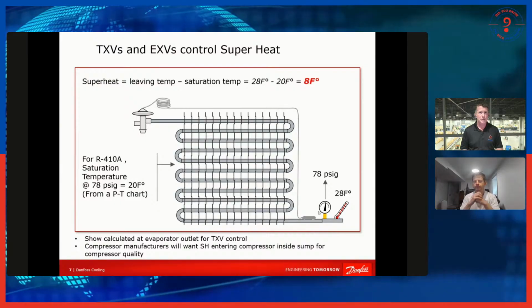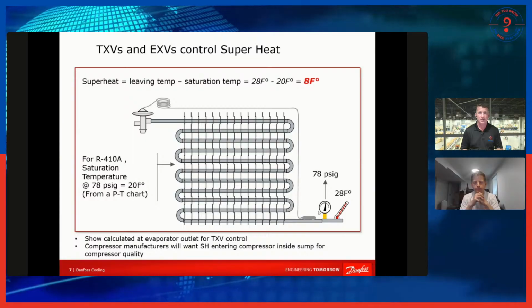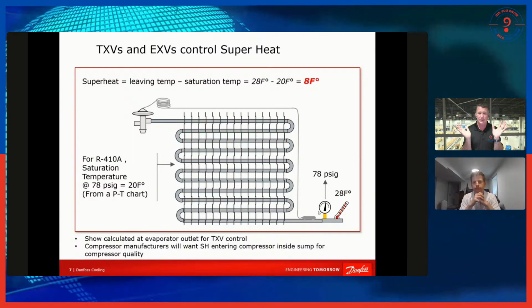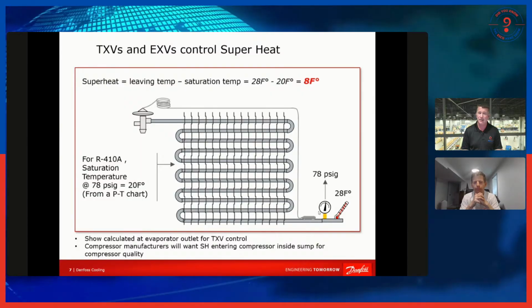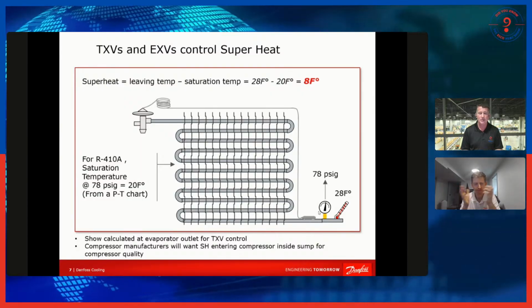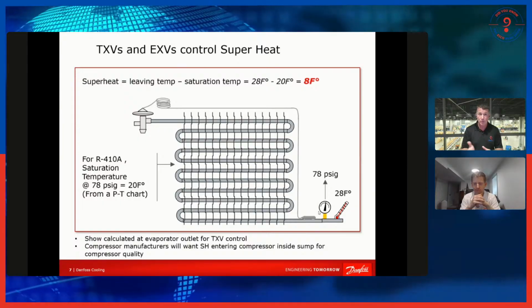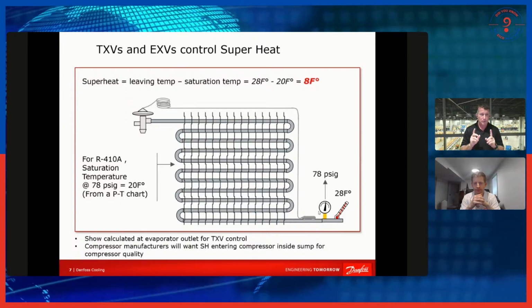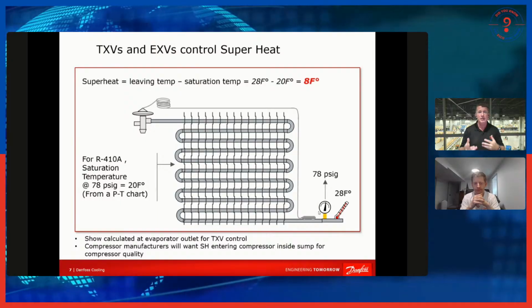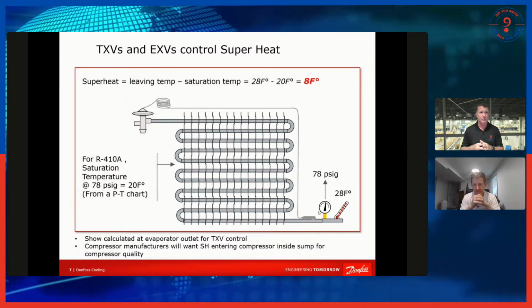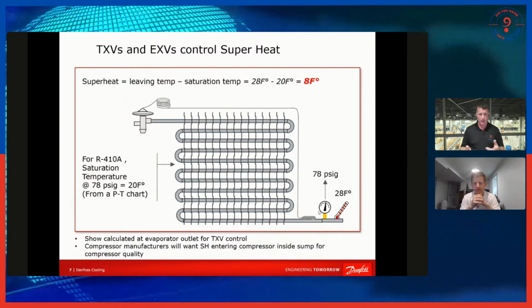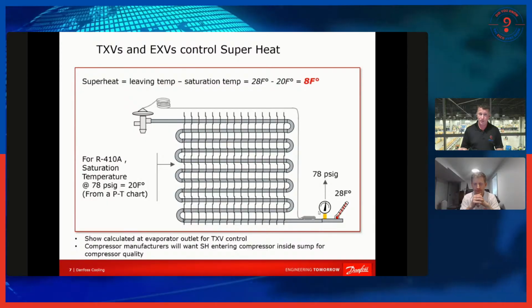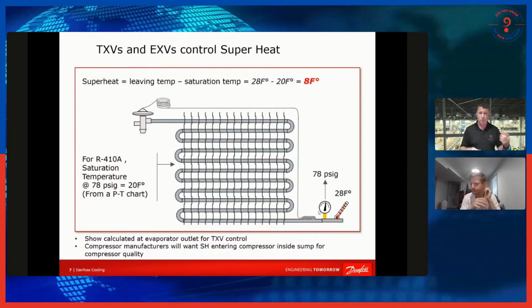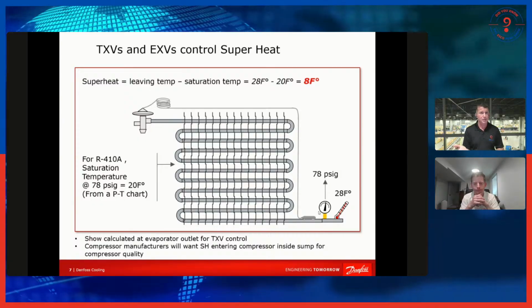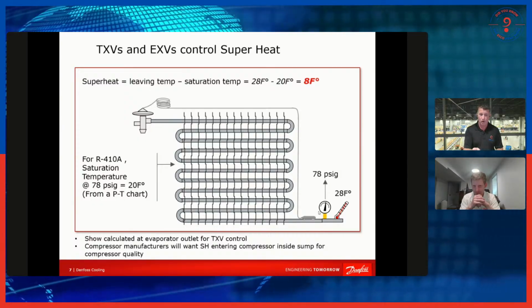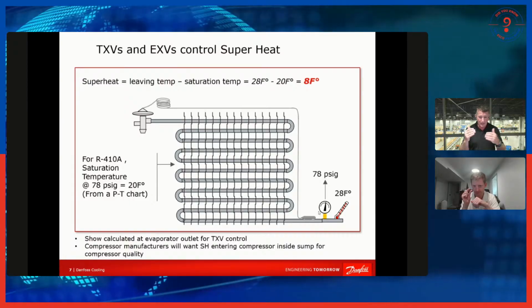So there's a general procedure within the industry for the placement of that sensing bulb. And we typically say between 10 and 2 on the top side of the tubing, but that's not always the case. It depends on exactly where the manufacturer wants that to be, especially when we're talking about blended refrigerants. So this is a very timely conversation when we start thinking about our transition into A2L refrigerants. You're going to be working with a blended refrigerant that has a little bit more glide than we have seen in the past. Every 400 series refrigerant is a blended refrigerant, potentially has some glide. R410A had a little bit, right? So we had very little glide.